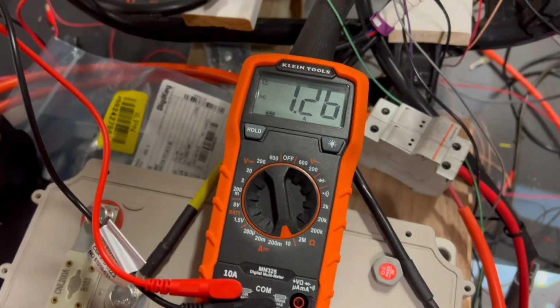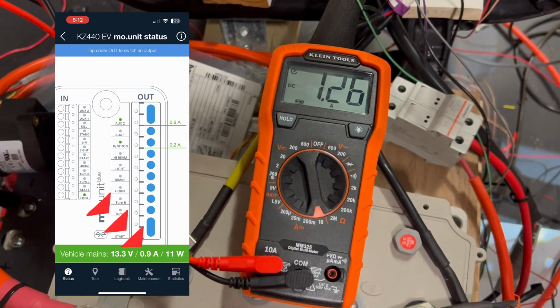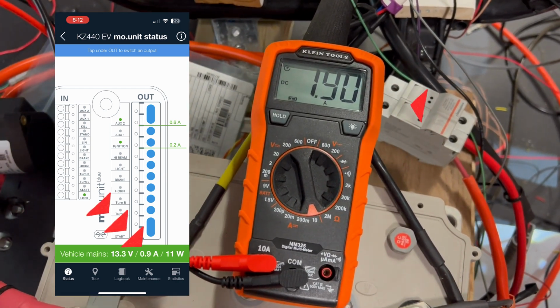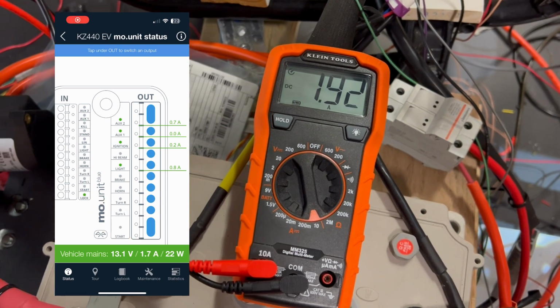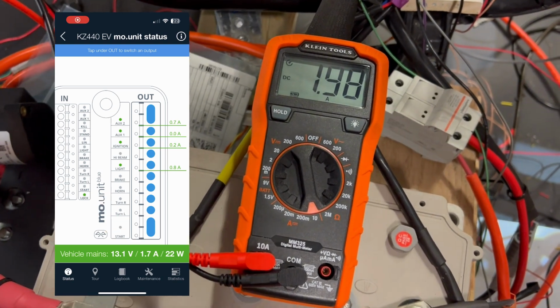I've added a temporary tap to the DC converter output to compare the actual current draw to what the Mo app is showing. If these are similar, then the DC converter should be the priority source for power over the backup battery, which is exactly what we want.